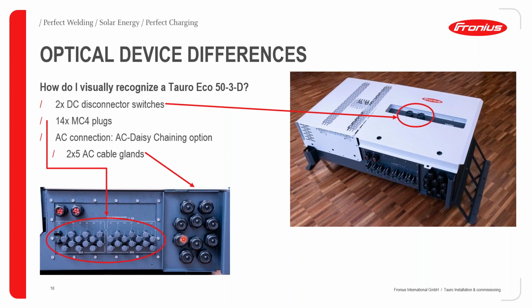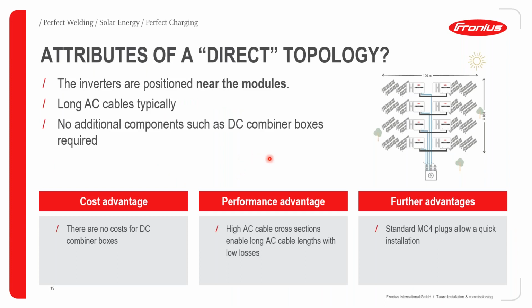You basically know that this is an inverter that can achieve AC daisy chaining. Because you come with your AC input from the bottom, for instance, and then to the next inverter, you're going to go with the next set of three-phase cables. So you can see here we have phase 1, 2, and 3, and then live, neutral and earth cables going into the next inverter.